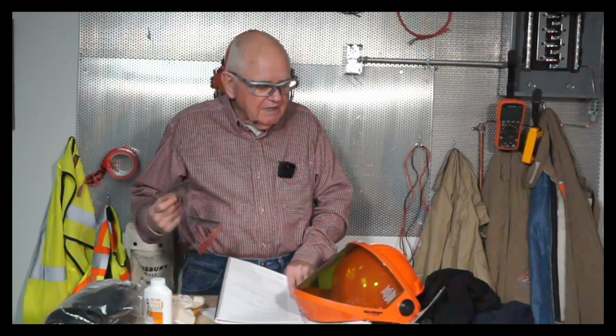Next topic, let's get into the PPE itself. I need to select the PPE if I'm using that incident energy analysis method. My PPE in this case, based on that label we just saw, would have to be rated for 3.5 calories. Now, we're probably not going to have any problems with that because our everyday work clothing is usually rated for a minimum of 8 calories. There's an informative annex in the back of 70E that gives you some information on recommended everyday work clothing. The reason I like to wear a minimum of 8-calorie clothing for everyday work is it probably covers 99% of the jobs I'm going to do. In the event that I'm going to work on something over 8 calories, then I can put on an arc flash suit or whatever I need, whatever my policy says, and protect myself at those higher incident energy levels.